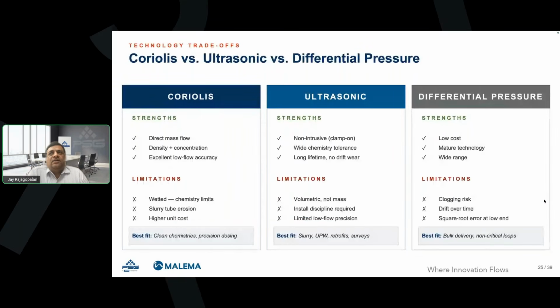Coriolis, ultrasonic and differential pressure type of flow technologies. Strengths: obviously, Coriolis measures mass flow directly, and it also measures density. You can interpret concentration of the fluid. An excellent low flow accuracy. The limitations are higher cost. Abrasive slurry can lead to tube erosion, which can lead into imprecision. So you have to select the Coriolis for the right application. High viscosity application is a great choice.